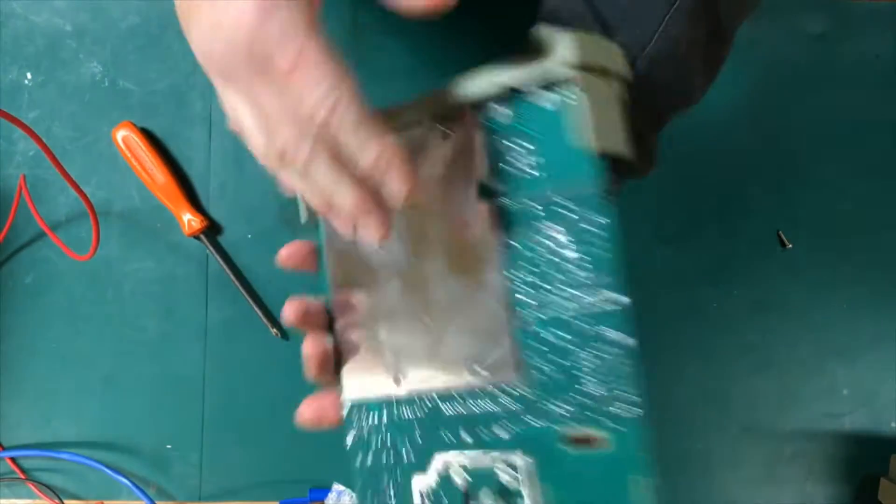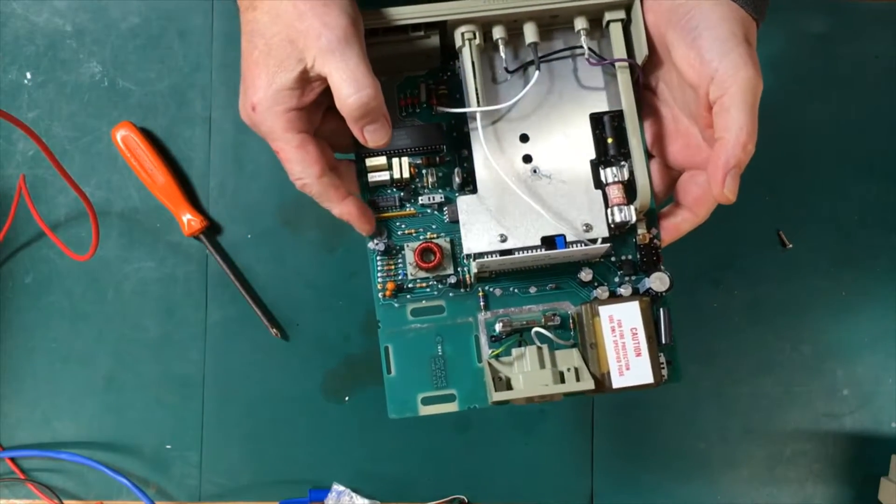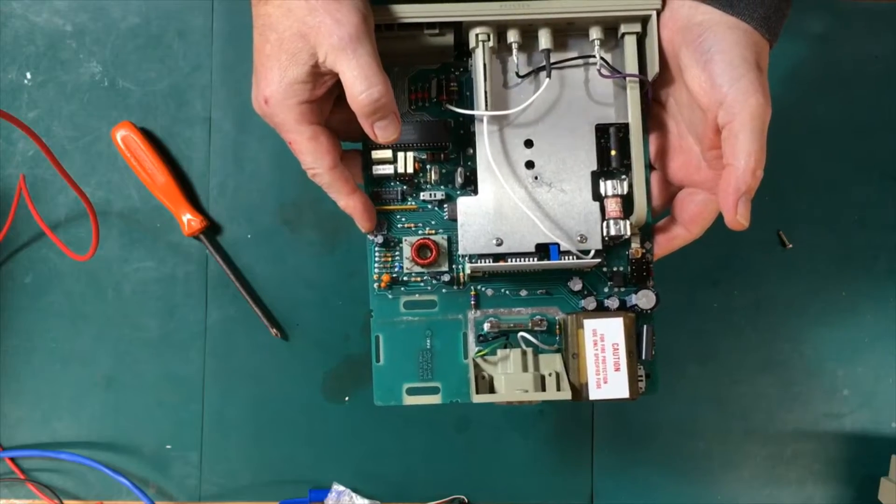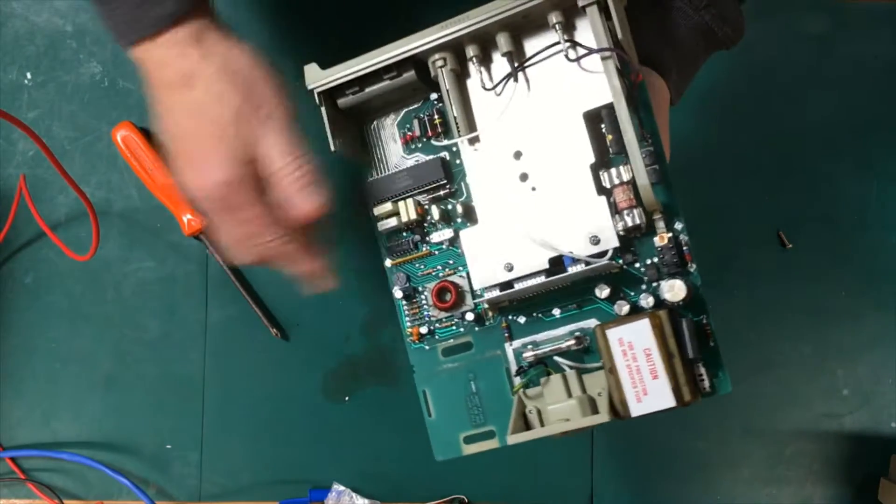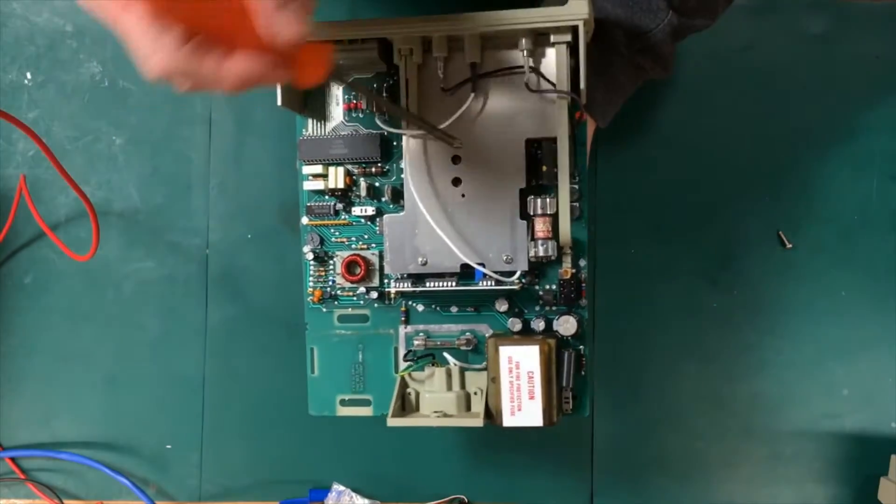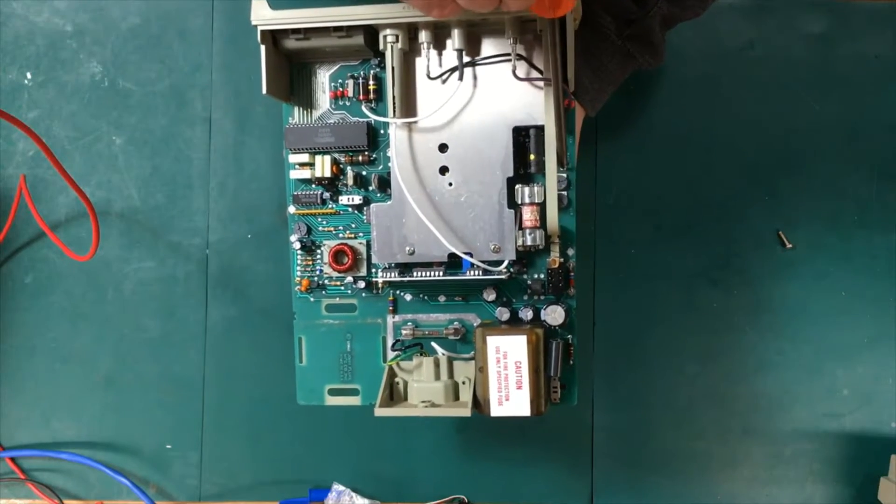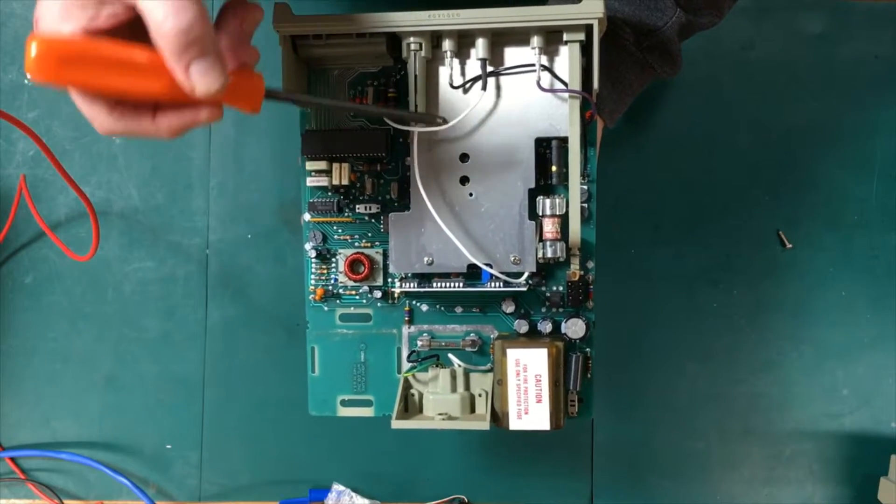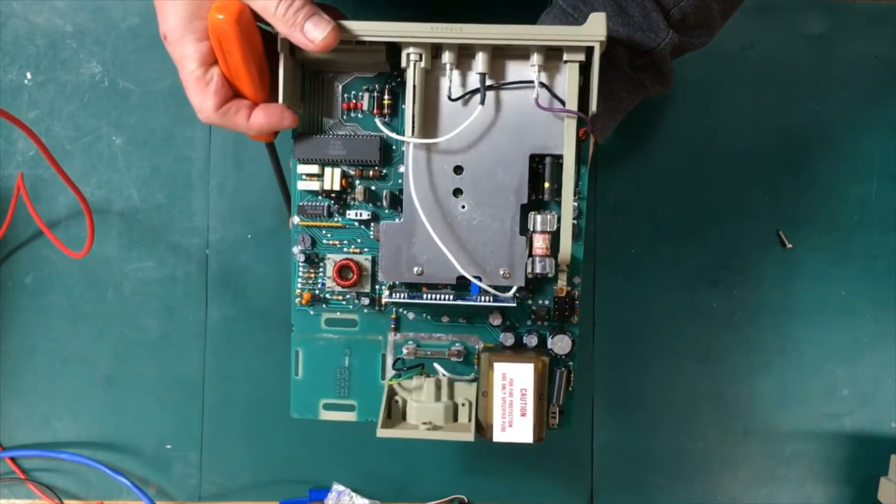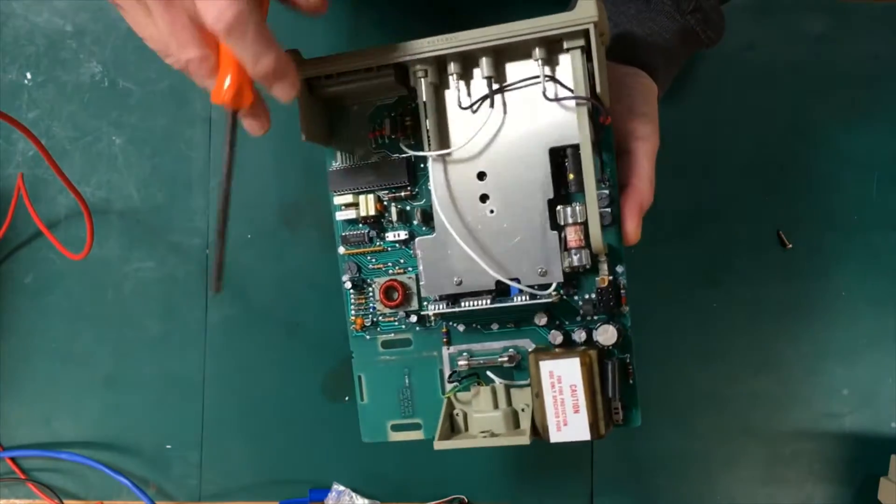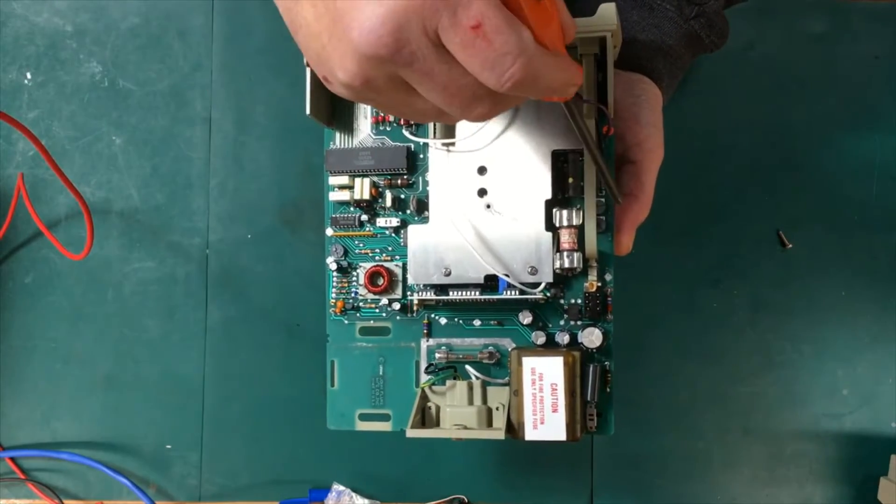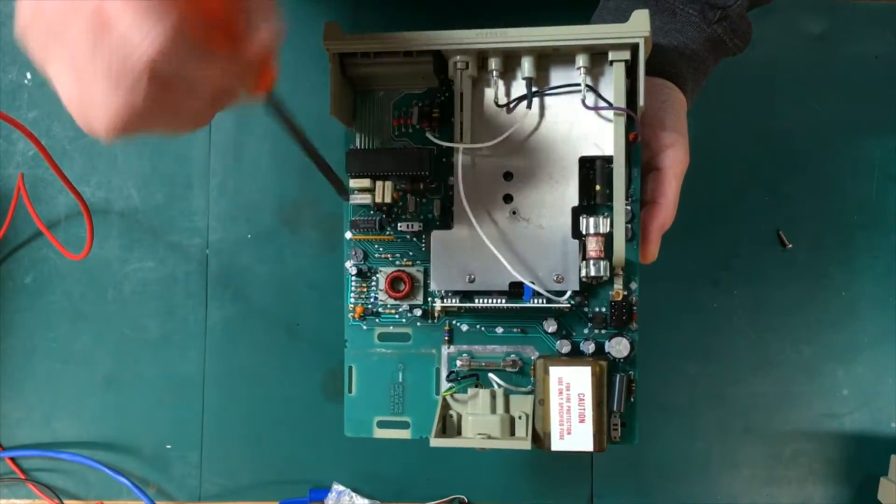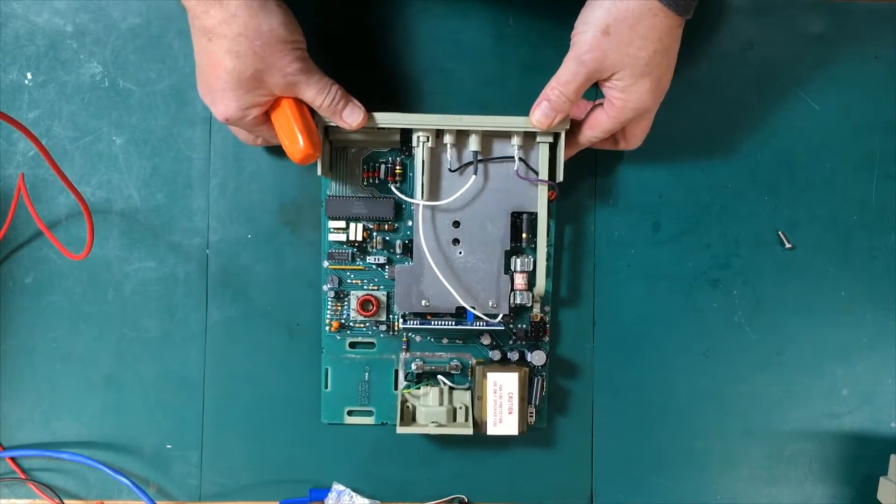When the meter's right side up, this right here is the little potentiometer that we have to use to calibrate the DC. Now the AC calibration is done with these two pots here and these two capacitors here. The two pots are for the low frequency AC and the two capacitors for the high frequency AC. It's actually a real pain to do that calibration because these two pots are interdependent, and these two capacitors are interdependent. Once you change one you have to go back and change the other, so it's back and forth. I'm really glad that the AC tested out just fine on this.